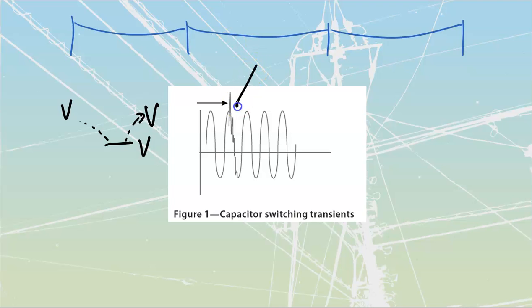Whenever they switch these on and off, there's a brief disturbance, usually less than one cycle long, but it gives ringing — almost like a ringing noise — which can cause multiple zero crossings. It drops down and hits that zero axis with really rapid back-and-forth movements, causing surges because of all the expanding and collapsing fields in the transformers on the system.